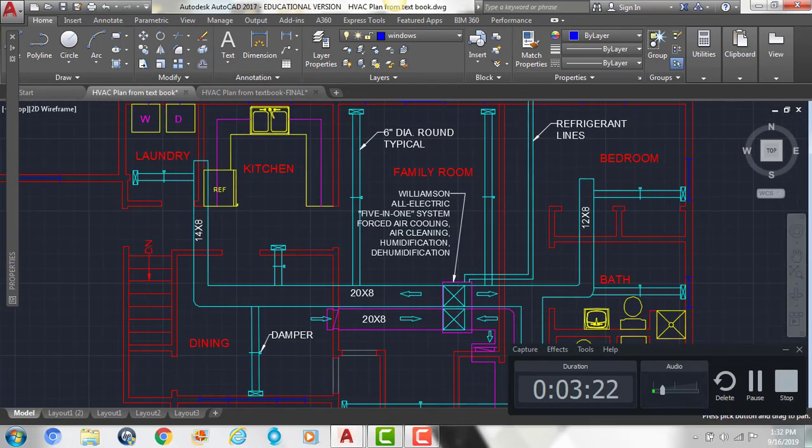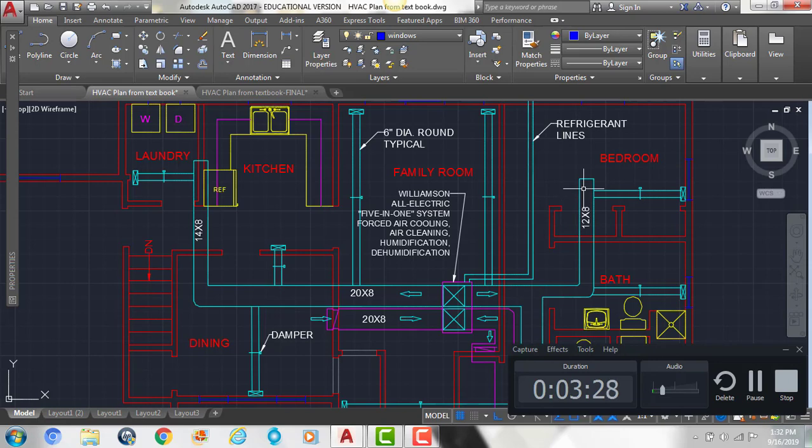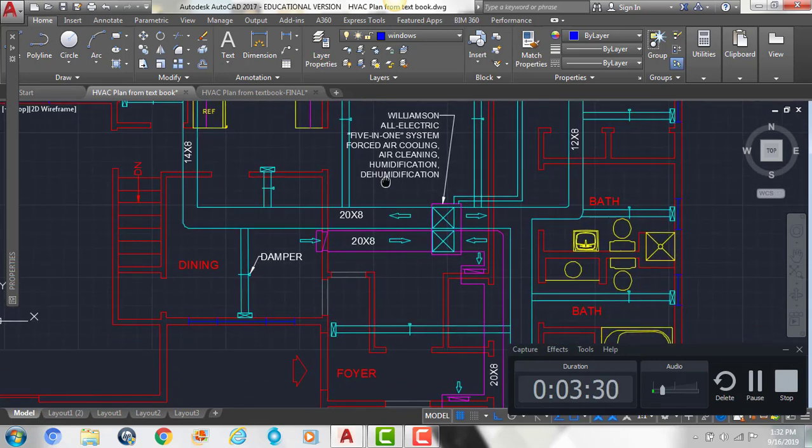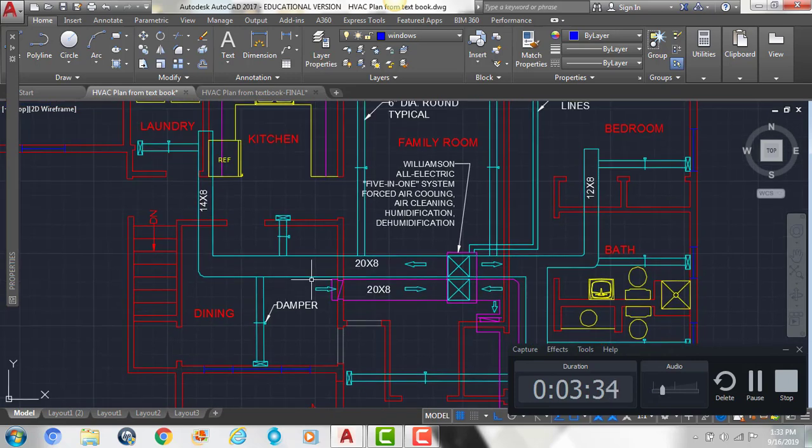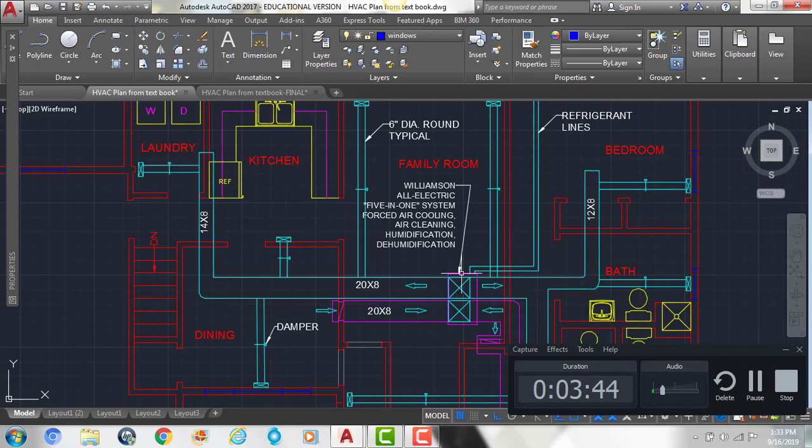So if we look at our handout, we can see we have large duct running along here. So the blue is going to be our supply air, and then the pink is our return air. We can see right here we have a 20 by 8 size duct, and then we have 14 by 8 and 12 by 8. It gets smaller as it gets further away from the heating system.